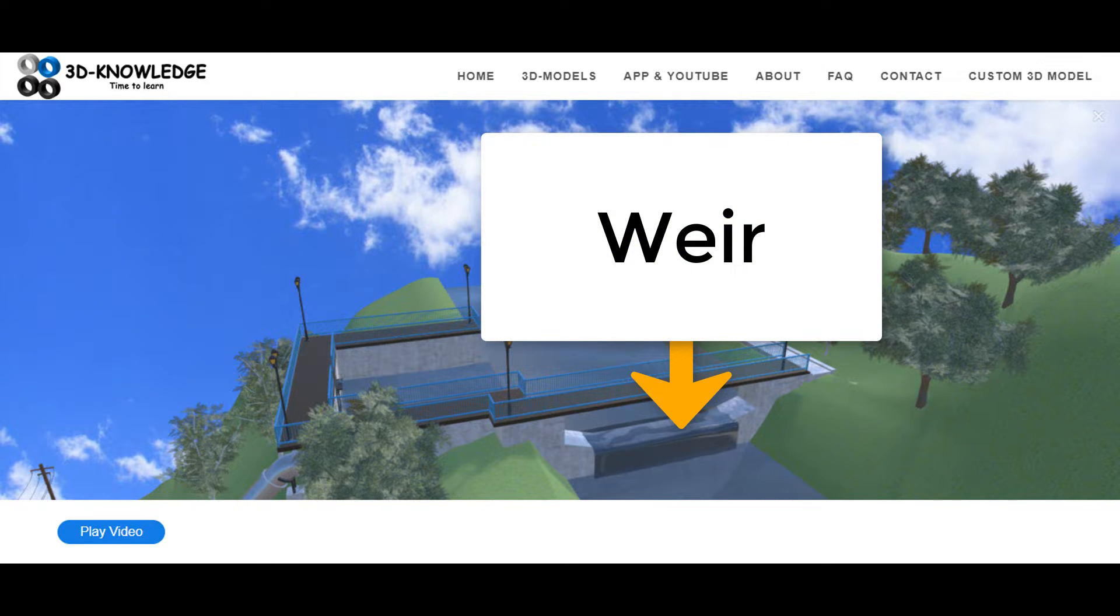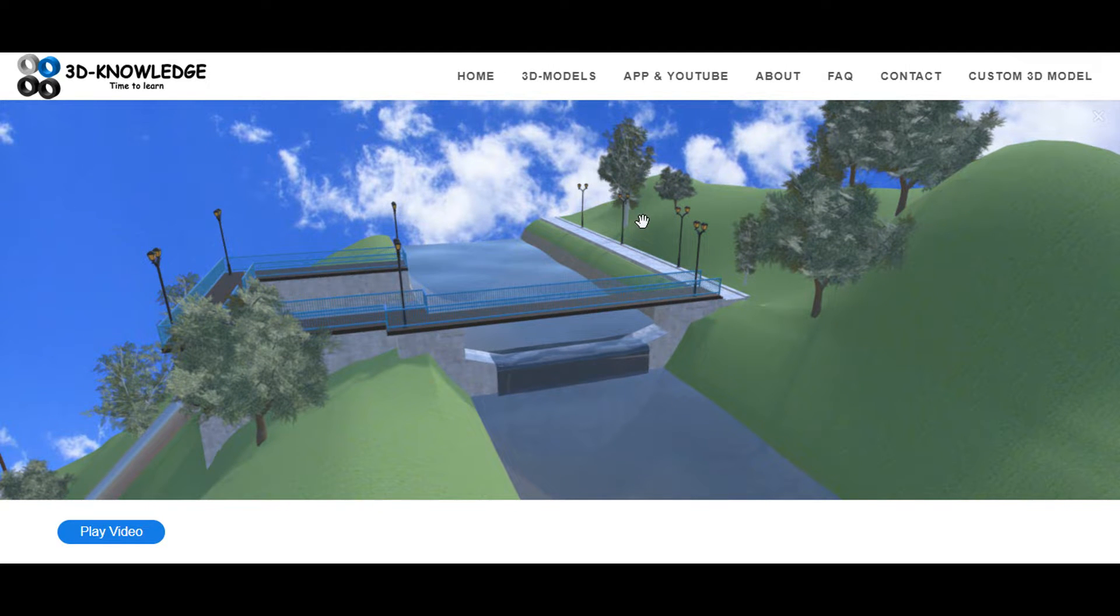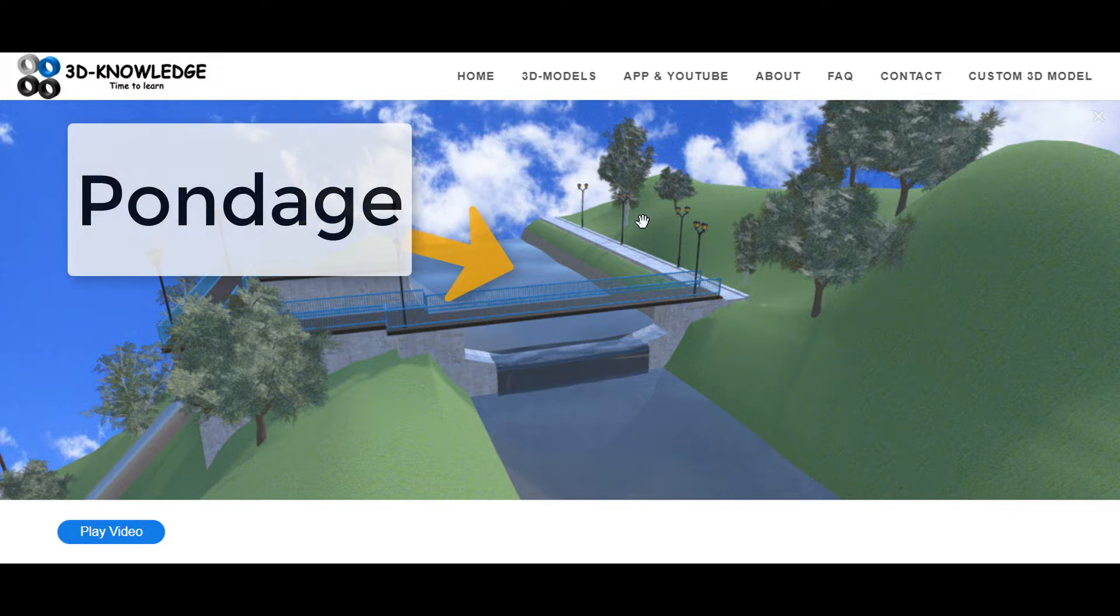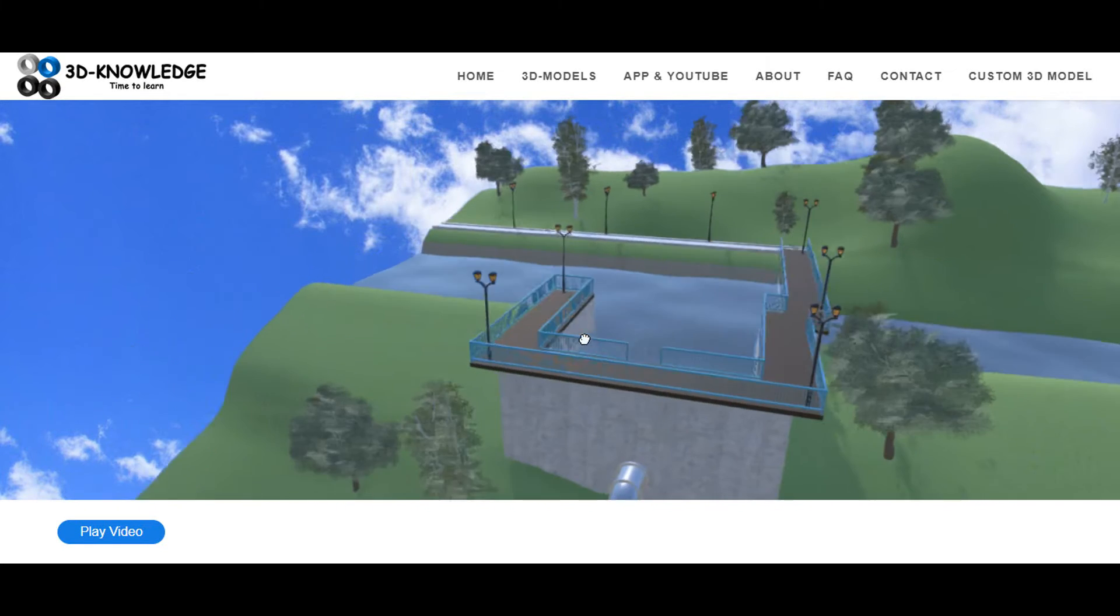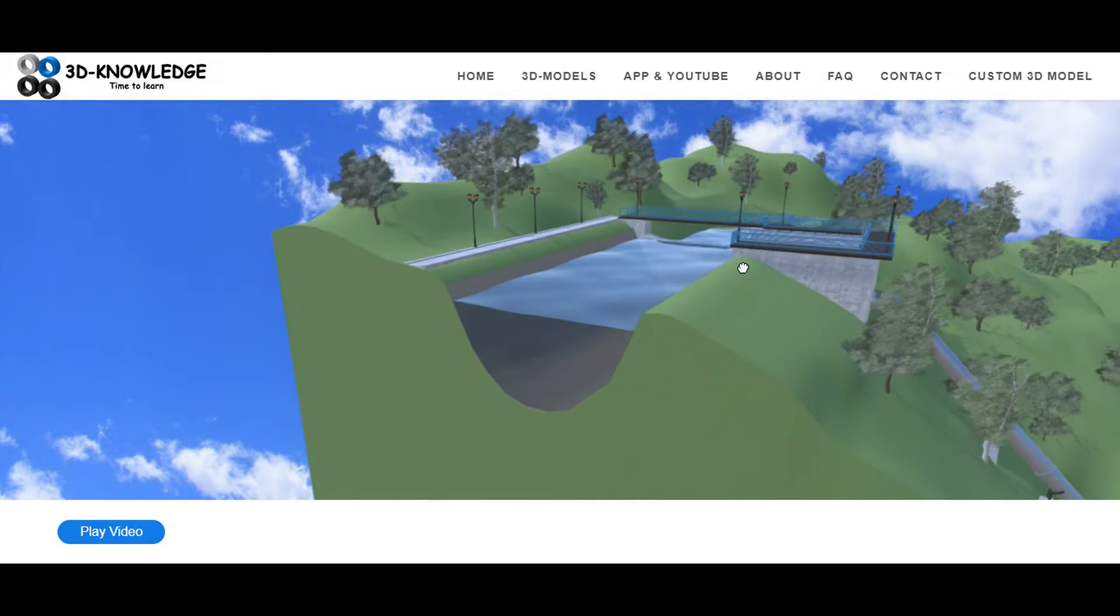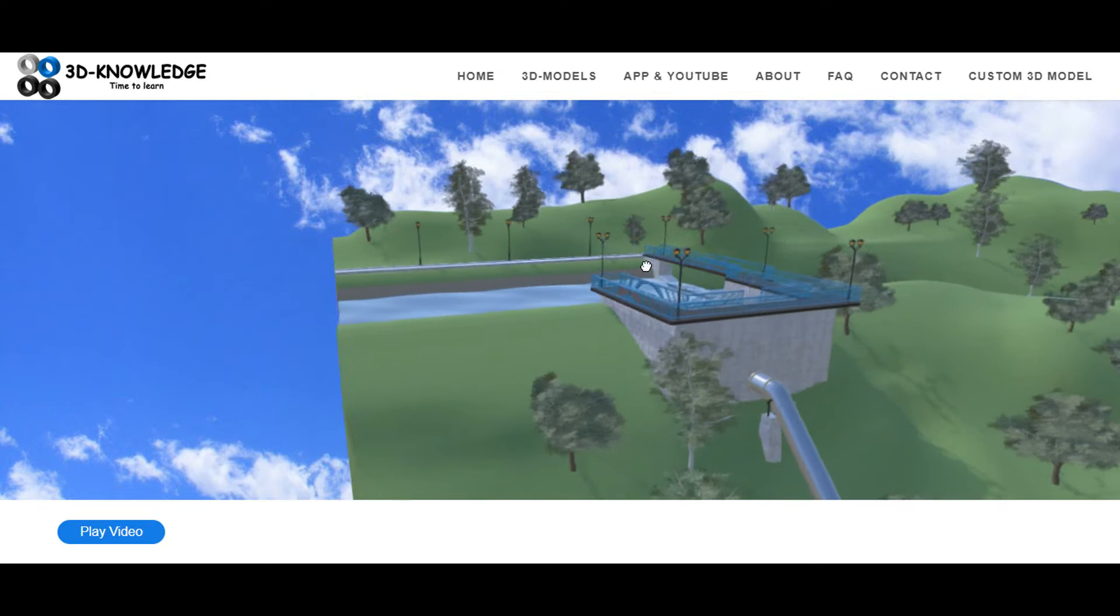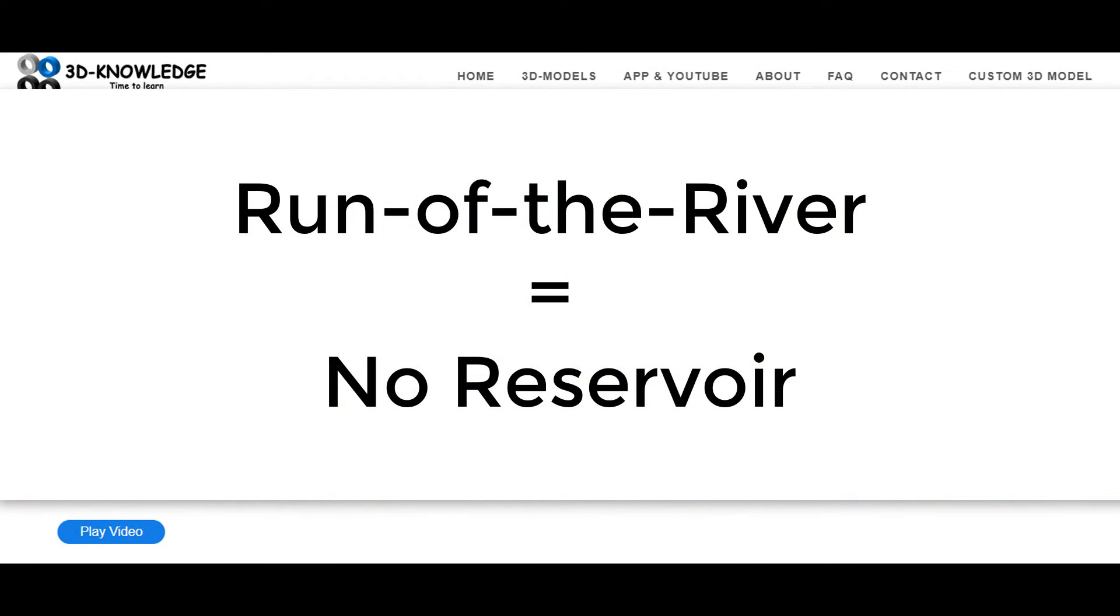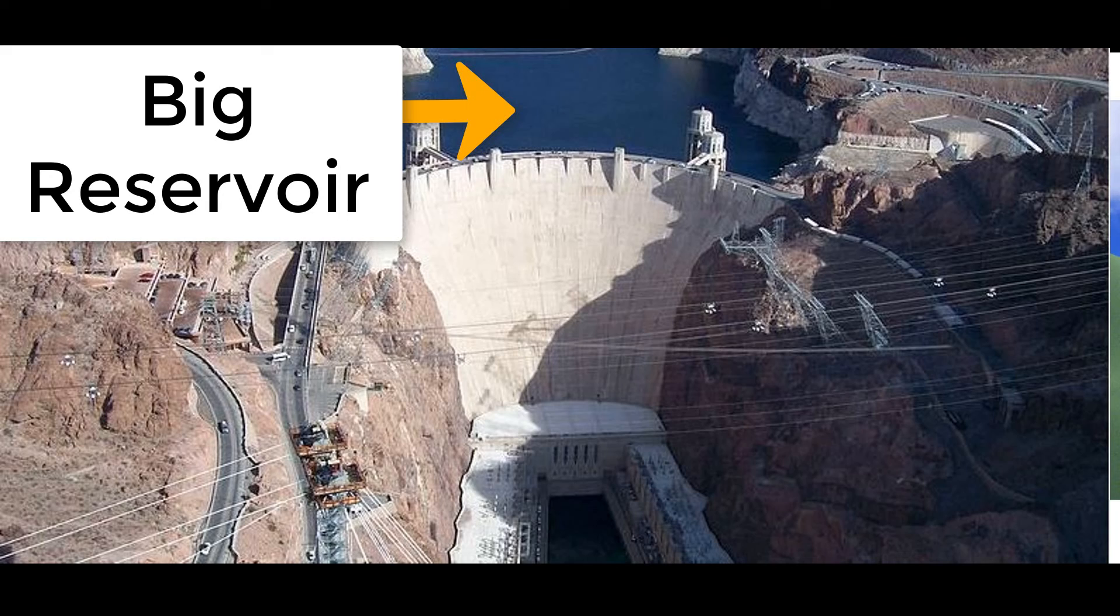Now we use the weir to create a body of water at the top and we can use this body of water to create a reliable water head or a reliable head of pressure down to the turbines. The actual name for the body of water behind the weir is called pondage. One of the differences between this and other types of hydroelectric power stations is that the weir allows the water to flow over the top so the water flow can continue, whereas a dam stops the water flow completely and builds a reservoir.